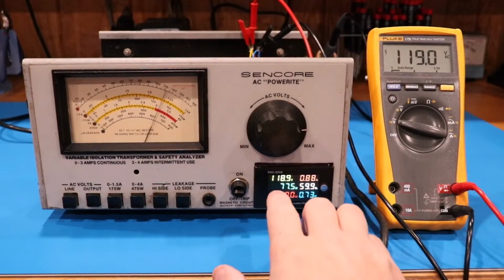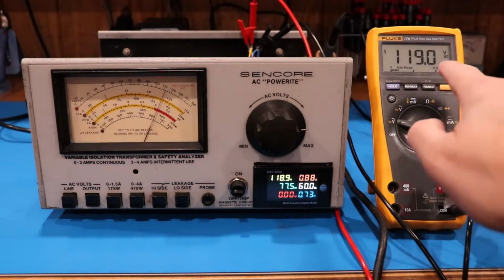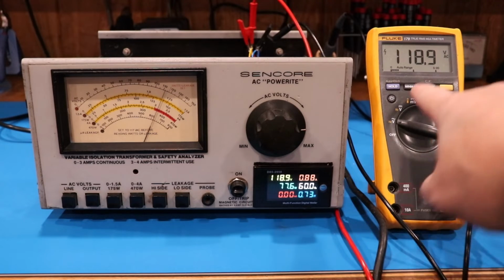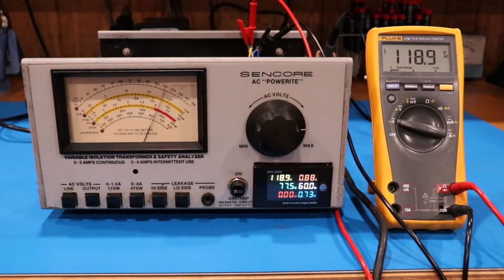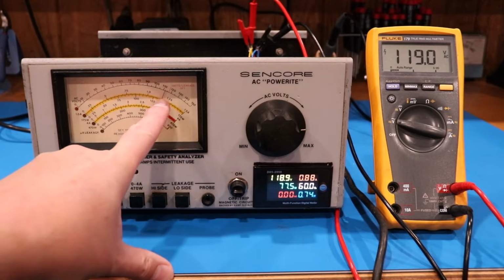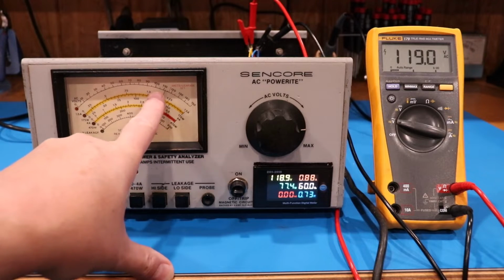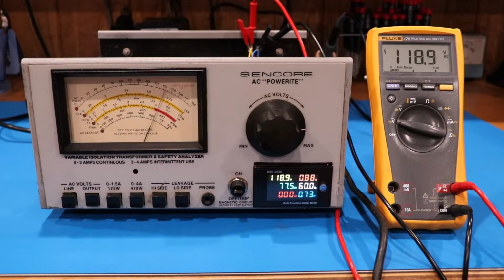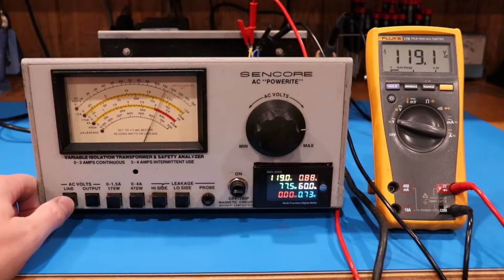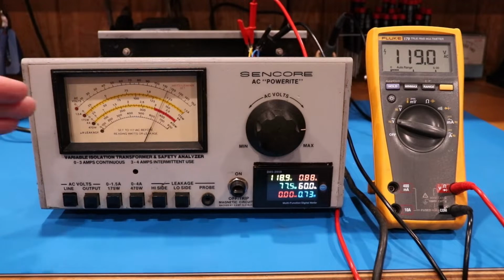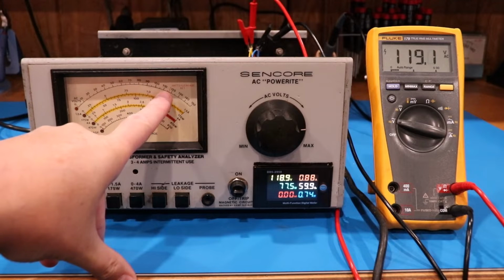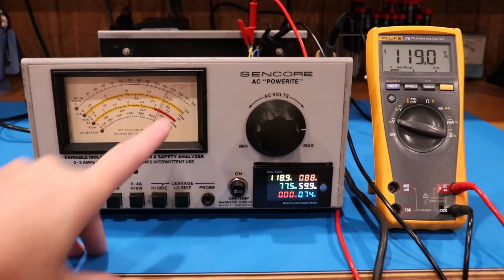But if you'll notice here, we're at 118.9, we're at 119, you can see it's bouncing around. We're pretty accurate here on this, close enough for what we need. But as I come over here to the analog meter that originally came on this unit, it is reading about 112 volts. So not 118.9 or 119, 112. And if I look at the line input, so you switch this button, it shows you what's feeding into the Variac, right? It shows it sitting here at around 115 volts.